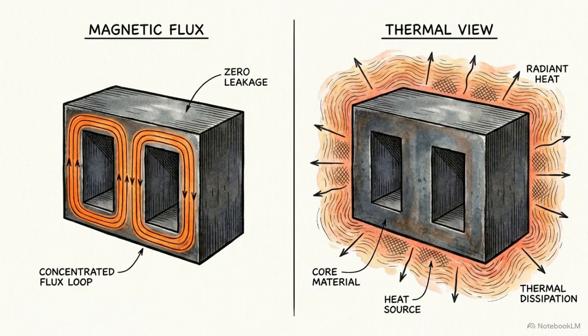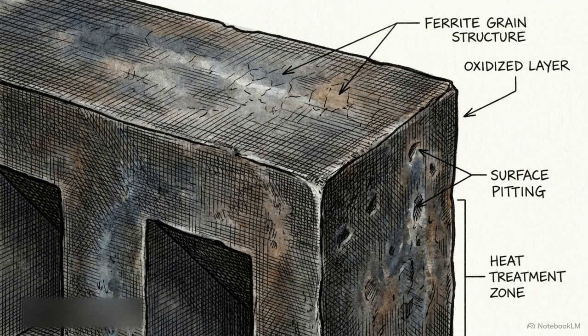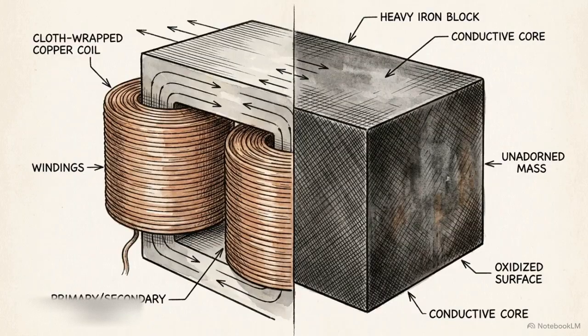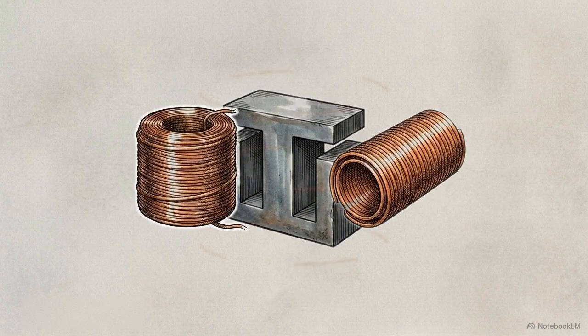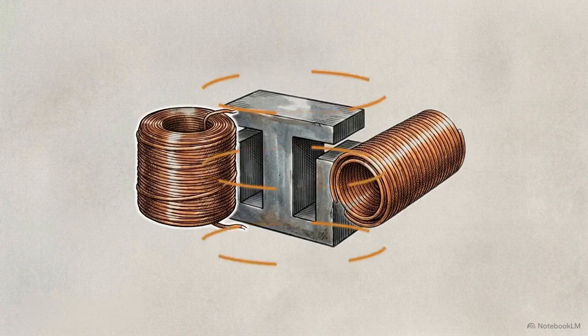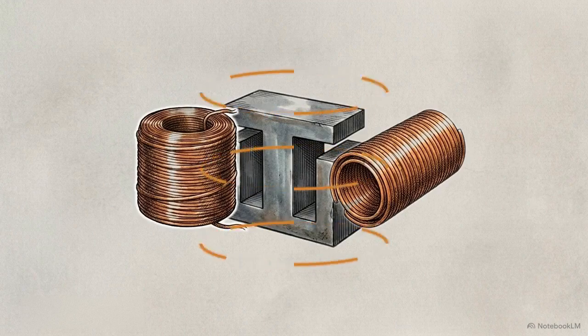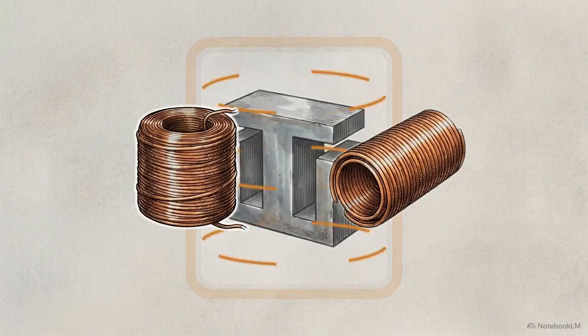Solving flux leakage binds the system to an inescapable thermal cost, illustrating how efficiency in one area often creates a physical penalty in another. The conductive nature of the steel core also introduces a secondary internal challenge. Faraday's law induces current in any conductor exposed to changing flux, and the core is a large block of conductive iron. The magnetic field induces swirling loops of electricity inside the core called eddy currents. Left unmanaged, their heat could melt the entire transformer.